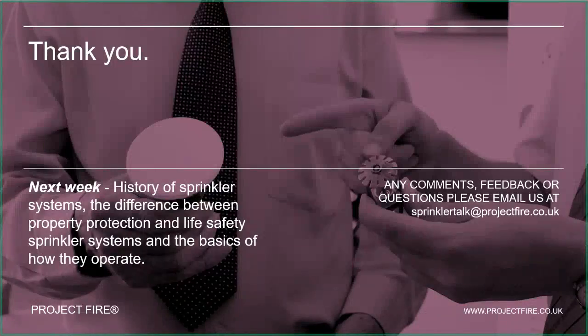Question: would commercial sprinklers cost more than residential systems? Definitely, in terms of cost per square meter. That's not so much to do with the heads, pipe, and fixings, but comes down to the water supplies. Commercial sprinkler systems require a much more expensive fire pump, a much larger water storage tank, larger fittings, butterfly valves, and more monitoring and electronics. So yes, a commercial sprinkler system will cost more than a residential system.